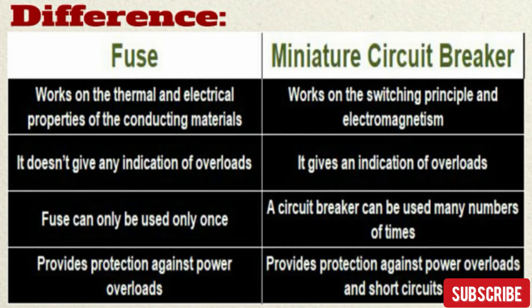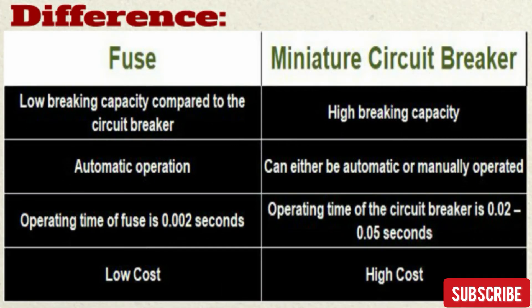Third, a fuse can be used only once, although resettable fuses are now available in the market, whereas an MCB can be used many times. Fourth, a fuse provides protection against power overloads only, but an MCB provides protection against both power overloads and short circuits. Fifth, fuses have a low breaking capacity compared to circuit breakers, but MCBs have a high breaking capacity. The operating time of a fuse is 0.002 seconds, while an MCB operates in 0.02 to 0.05 seconds.